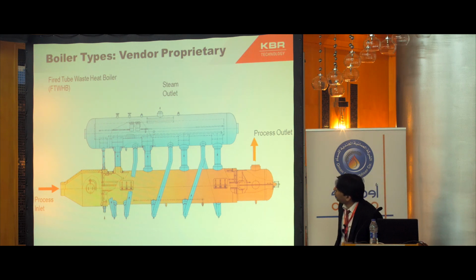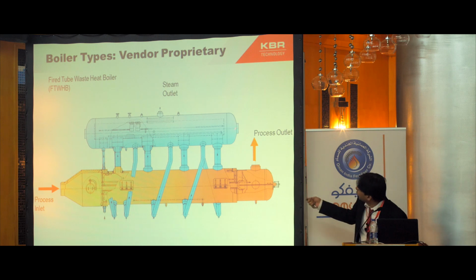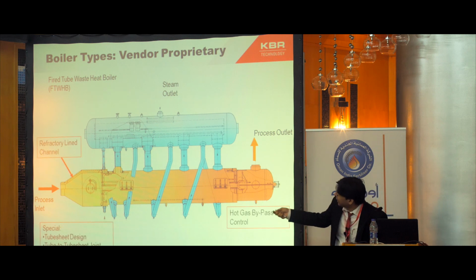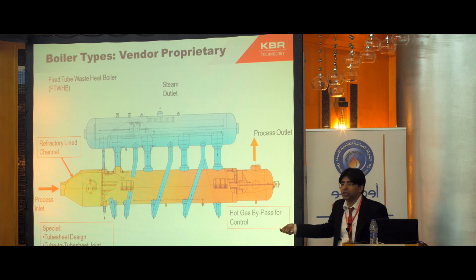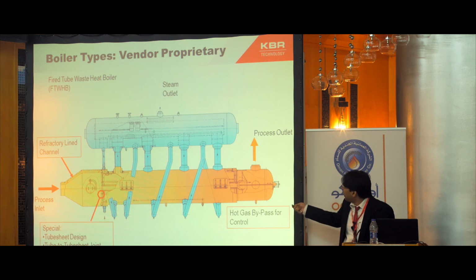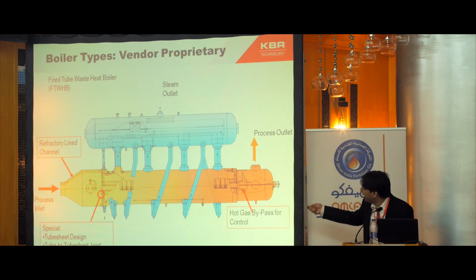Next is the vendor proprietary boiler fire tube design, horizontal, which is connected to the steam drum from the top. The process gas comes from the side. It is a refractory lined channel. It has a specialty in tube sheet design and tube to tube sheet joint. The internal bypass is provided for the temperature control, and the process outlet comes from the side.